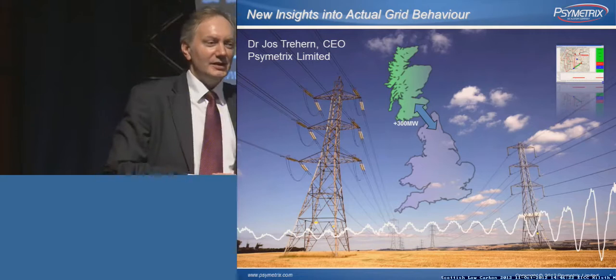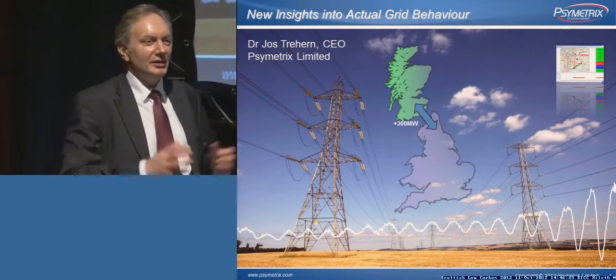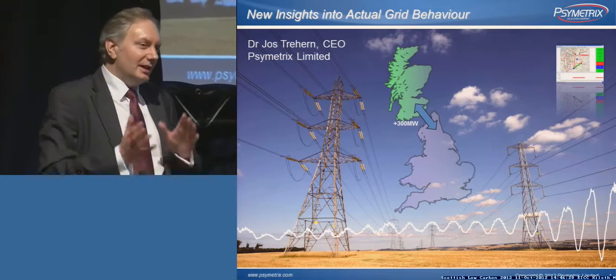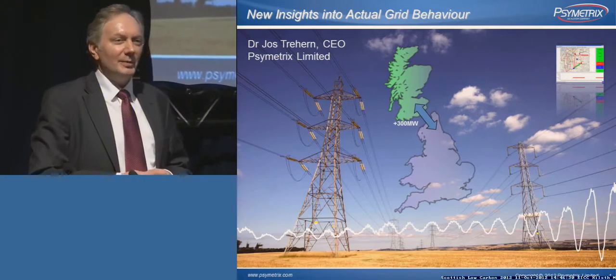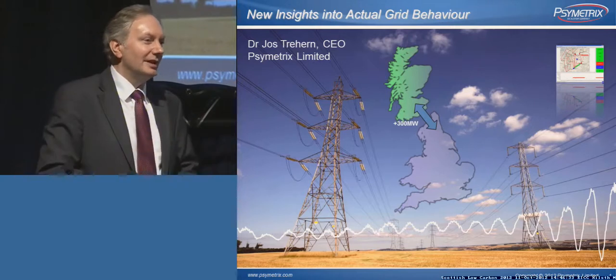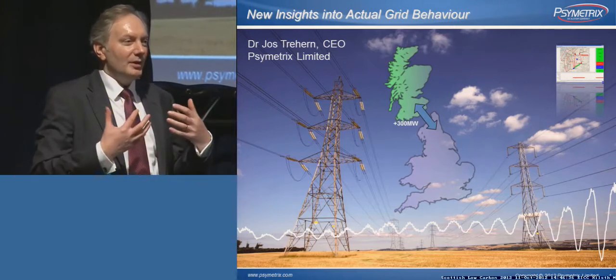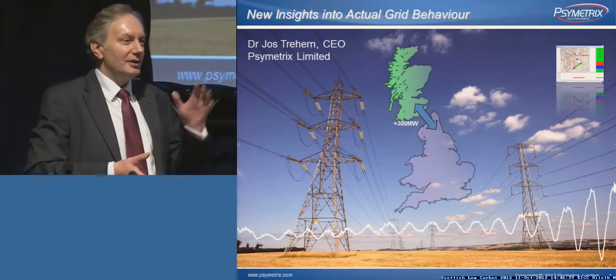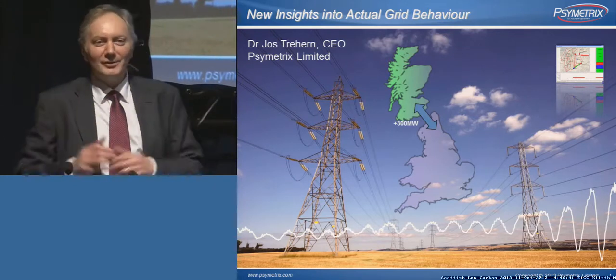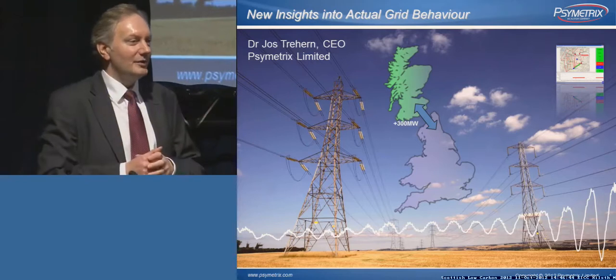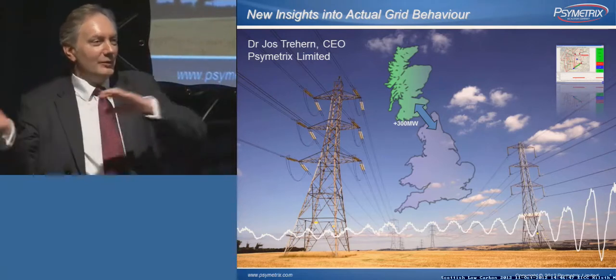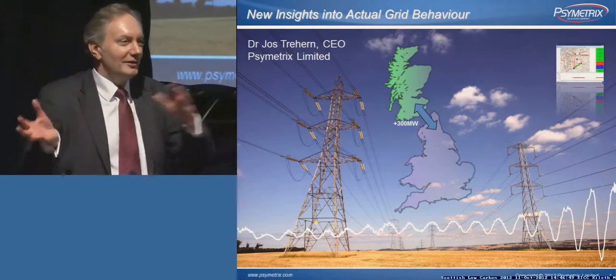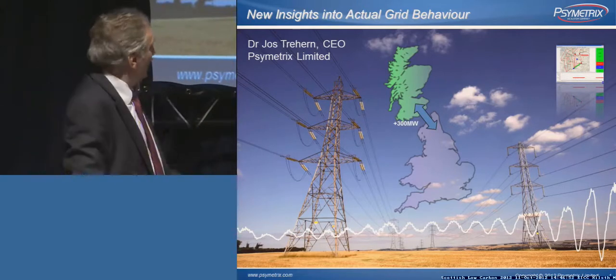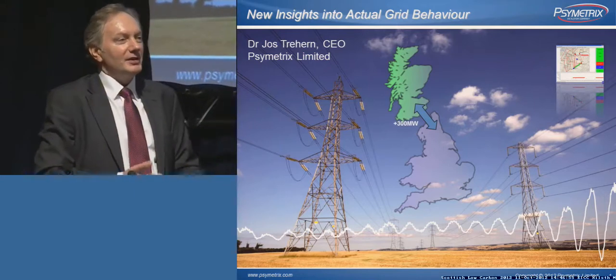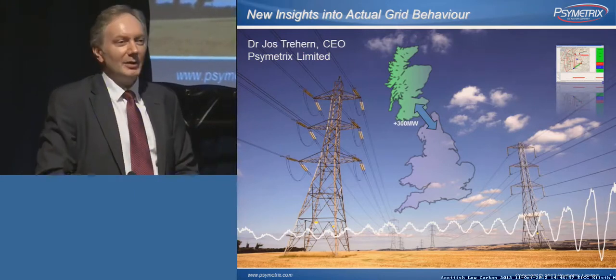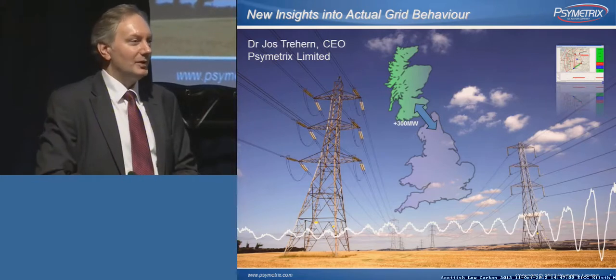In the mid-90s, the power system in the UK was being challenged because utilities in Scotland wanted to export as much energy into the English market as possible. But they were constrained by oscillations occurring on the system—very low frequency oscillations. In technical terms, this means huge amounts of energy rushing backwards and forwards from one end of the country to the other. If these oscillations grew, it would cause protection equipment to trip and people would have a blackout, so it wasn't acceptable.